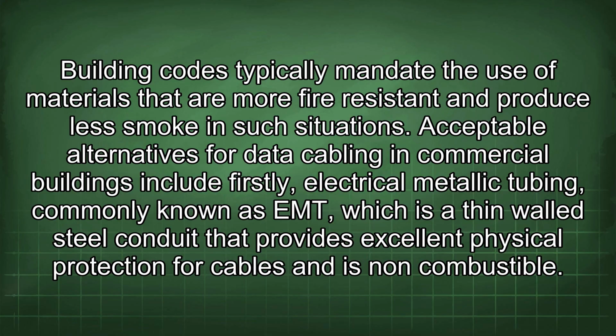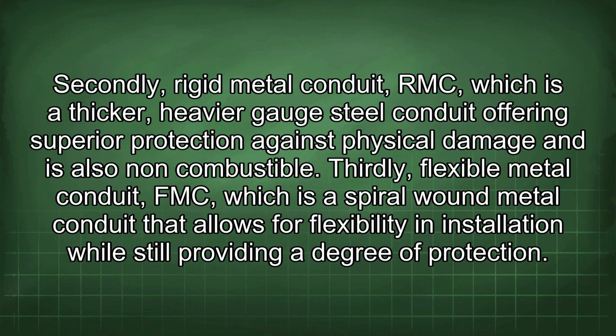Acceptable alternatives for data cabling in commercial buildings include, firstly, electrical metallic tubing, commonly known as EMT, which is a thin-walled steel conduit that provides excellent physical protection for cables and is non-combustible. Secondly, rigid metal conduit (RMC), which is a thicker, heavier-gauge steel conduit offering superior protection against physical damage and is also non-combustible. Thirdly, flexible metal conduit (FMC), which is a spiral wound metal conduit that allows for flexibility in installation while still providing a degree of protection.